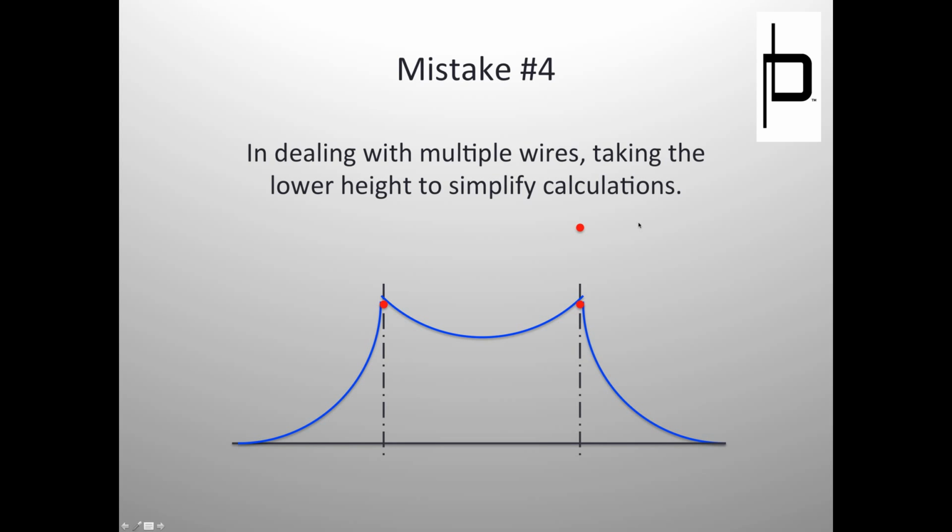I guess if your client wanted more height for their device, then you may want to keep the higher wire as well, so that there's more space of protection. Well, I would never recommend to my client to lower the wire. What I'm saying is, as I'm calculating it, for ease of calculation, it's easier to just assume these are the same height. But if my client has a wire here, I would probably say keep that wire there. I'd have to look at this side strike coming in and make sure that it doesn't roll underneath. But I would probably keep the taller wire height.